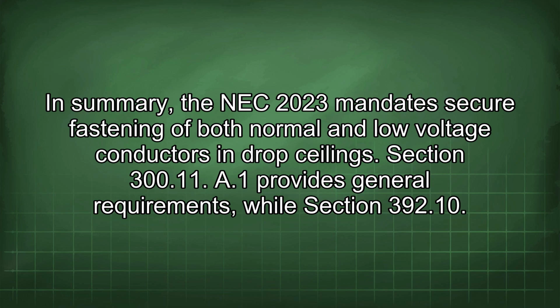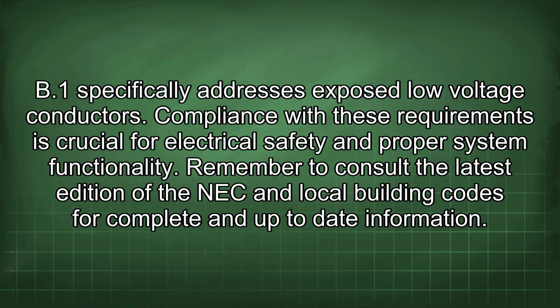In summary, the NEC 2023 mandates secure fastening of both normal and low voltage conductors in drop ceilings. Section 300.11(A)(1) provides general requirements, while Section 392.10(B)(1) specifically addresses exposed low voltage conductors. Compliance with these requirements is crucial for electrical safety and proper system functionality.